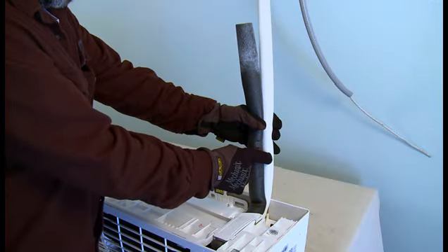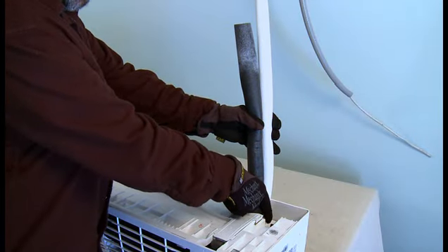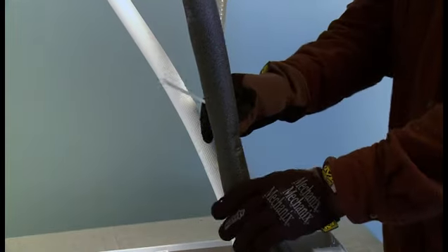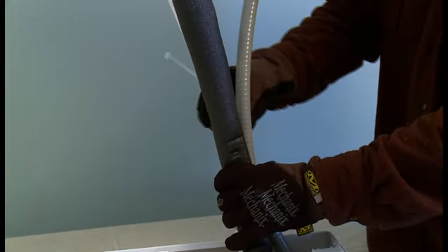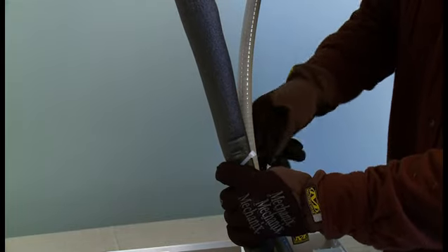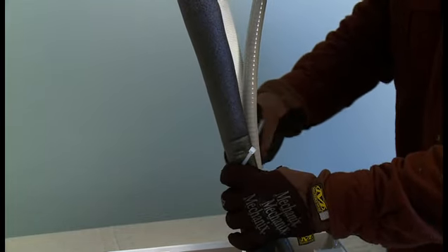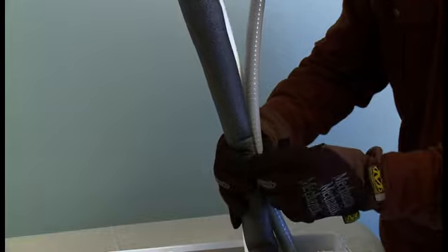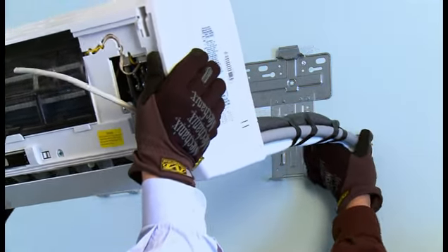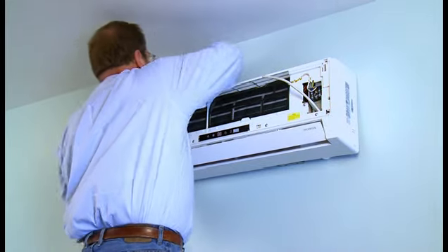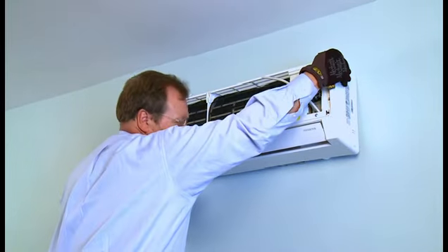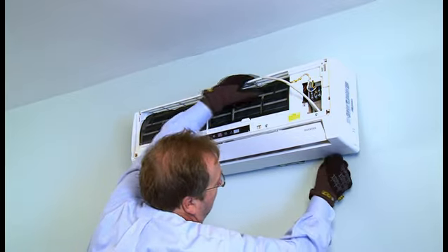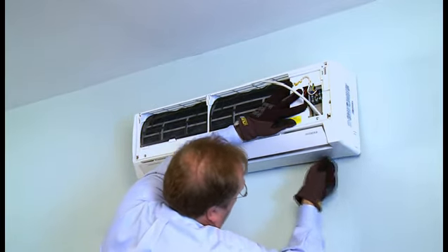We will now bundle together the control wire, drain hose, and line set. Note a portion of the line set is pre-attached to the interior unit. To make it easier to thread the pipes, drain hose, and control wire through the wall, securely bundle by using nylon cable ties. For proper drainage, be sure the drain hose is lowest in the bundle. Secure the bundle with tape. Now, with assistance, pass the bundled piping through the hole. Position the interior unit's upper claw over the installation plate's upper hook. Push in at the bottom of the unit to secure it at the two mounting tabs.